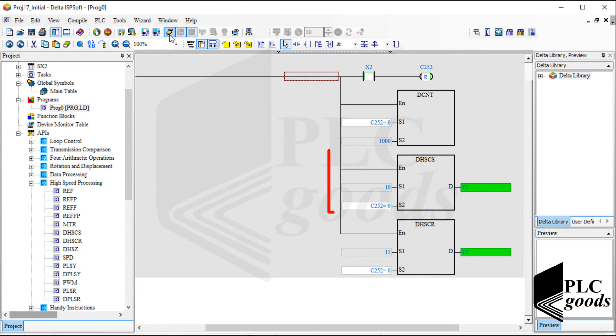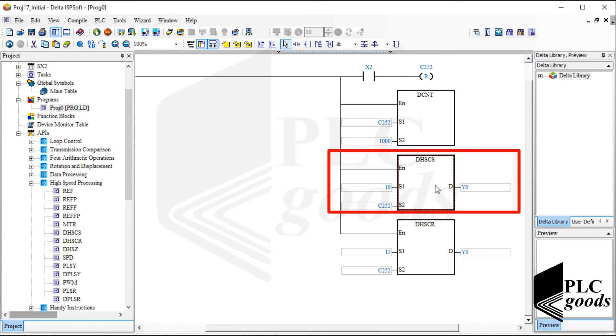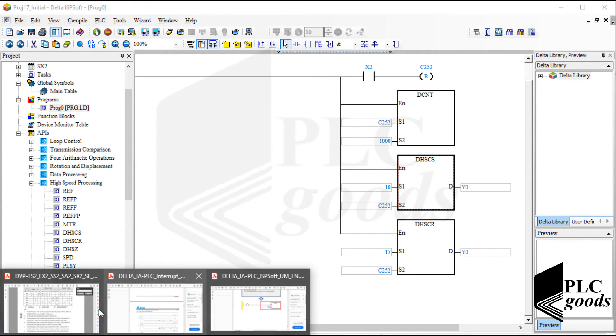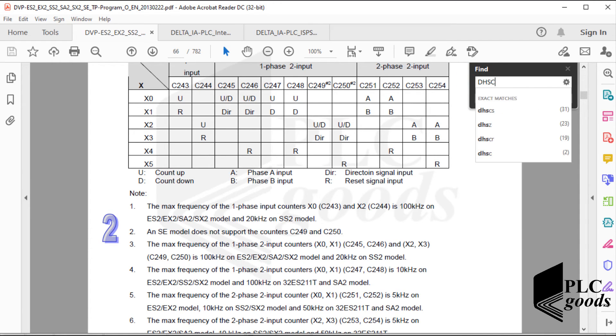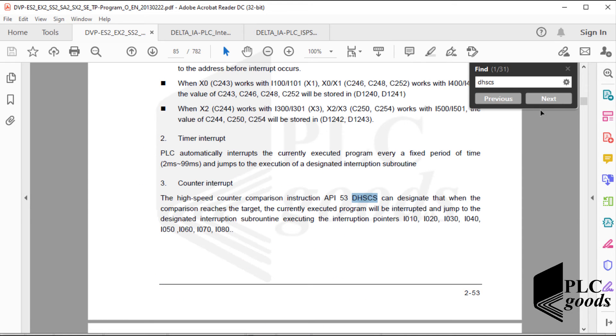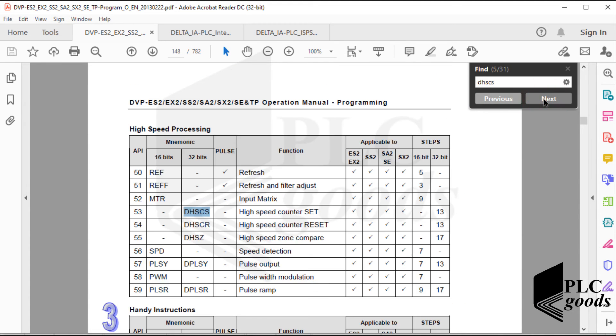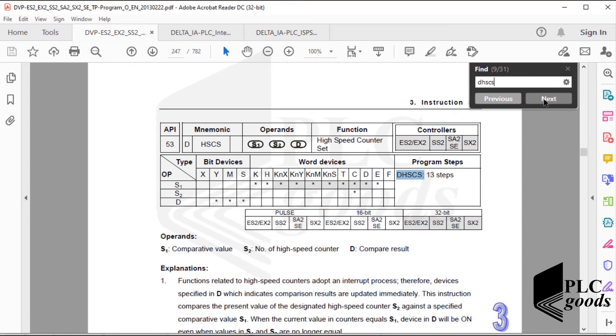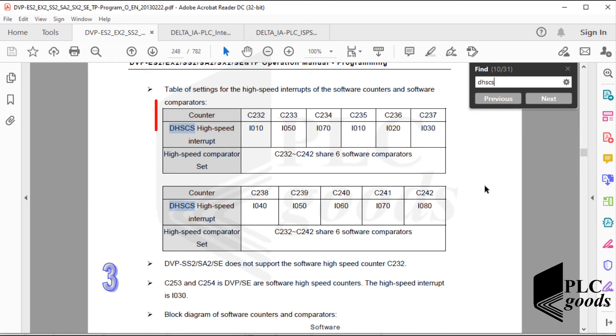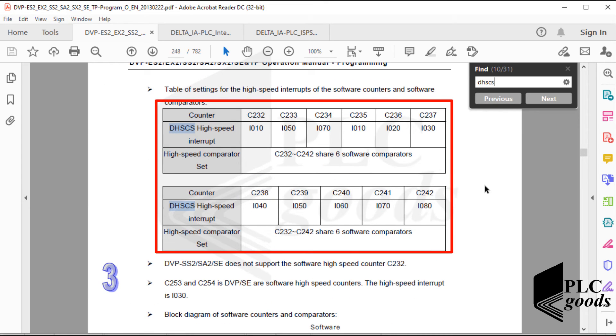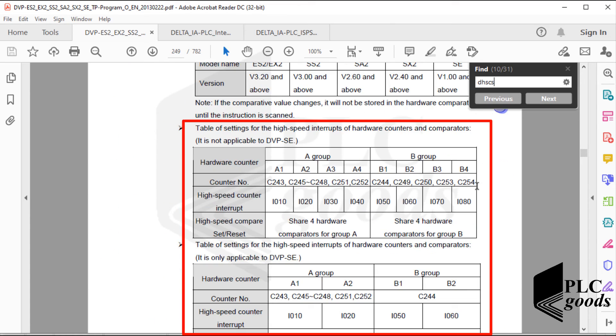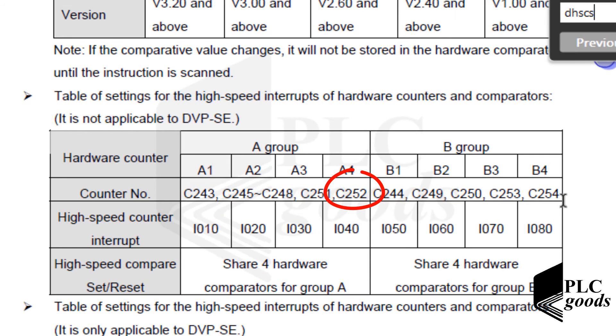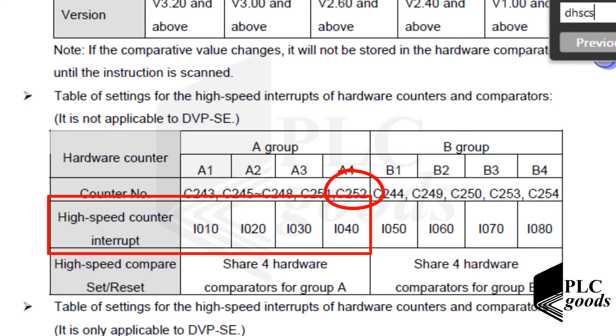Another useful point is related to the DHSCS instruction: it can be used to run an interrupt immediately instead of turning on an output. Let me search the DHSCS instruction inside the user manual. Here I can read the instruction description. These tables display which interrupts can be enabled by which software high-speed counter, and similarly we can use these tables for hardware high-speed counters. For example, the counter C252 used in my program can run these interrupts using the DHSCS instruction.